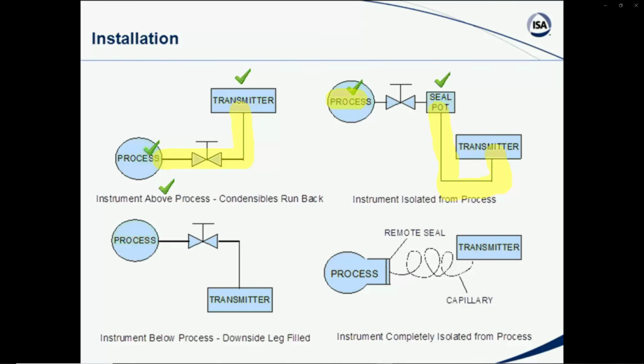Now, we would also have to be aware, though, that we do have a situation here, depending on the range, that that's a liquid-filled leg that our transmitter might be involved with as far as the calibration is concerned. It would depend upon the magnitude of the process pressure. Okay, what about this situation here where we have our process and we mount our transmitter below that particular device? Now again, we're isolated to some degree if we want to put a different fill fluid in, but also we would use this for a liquid situation where we'd have a liquid fill leg, and then any vapors or any gas bubbles that might be produced in that down leg would rise back up and into the process. So again, we could use a different liquid fill for that down leg, or we could actually use the process liquids themselves.